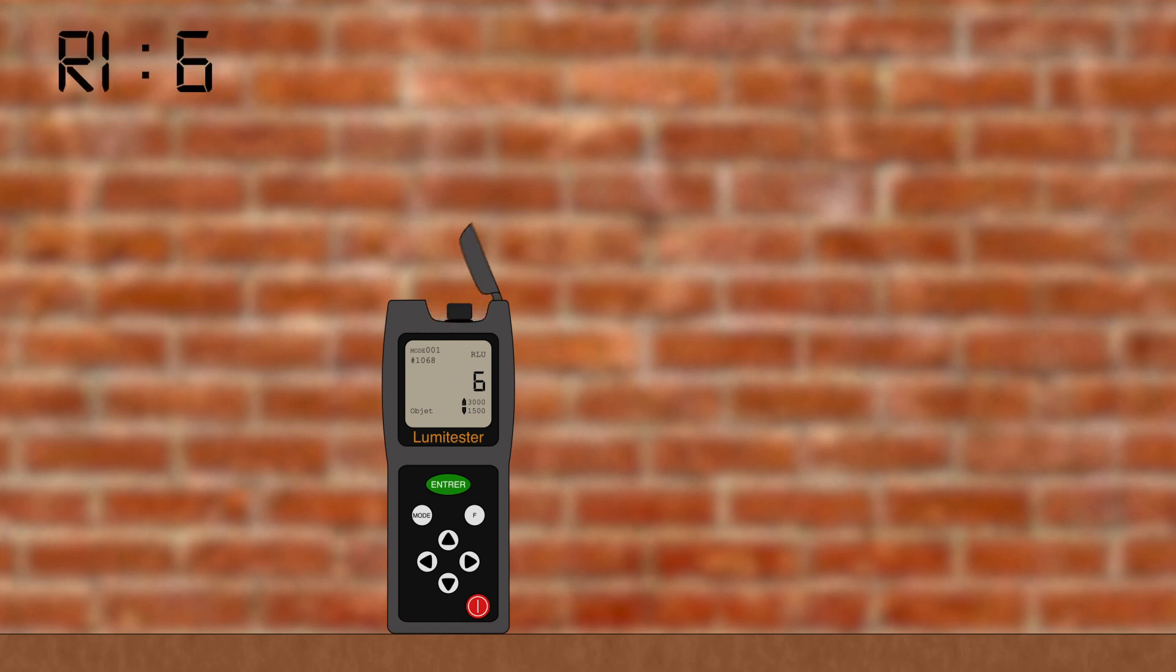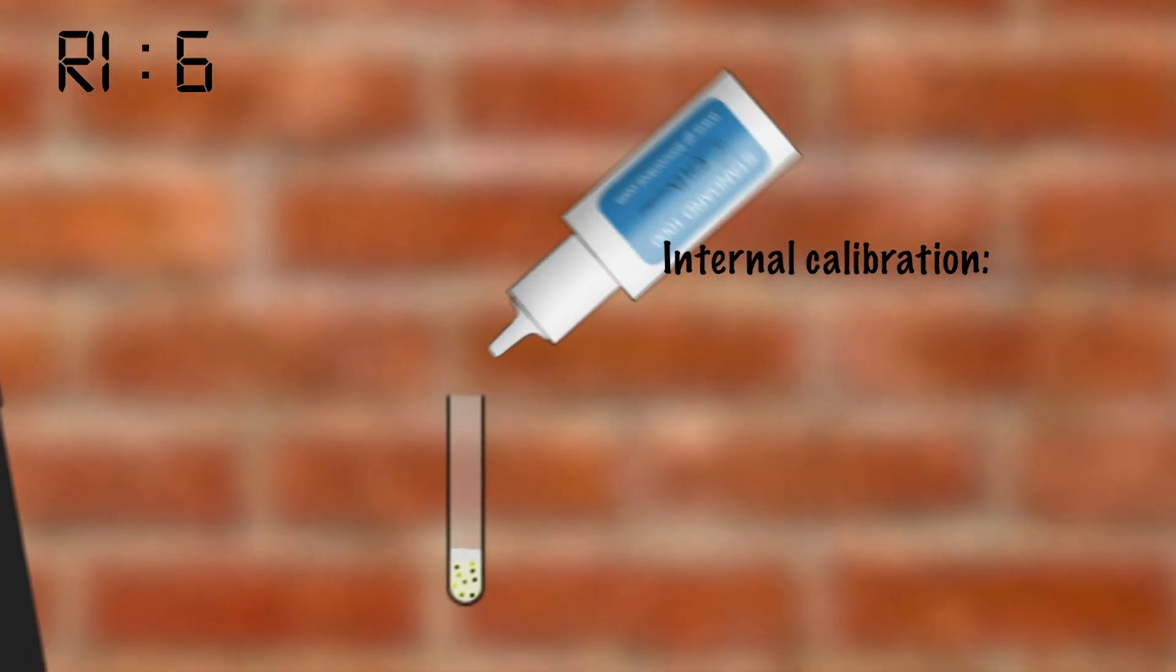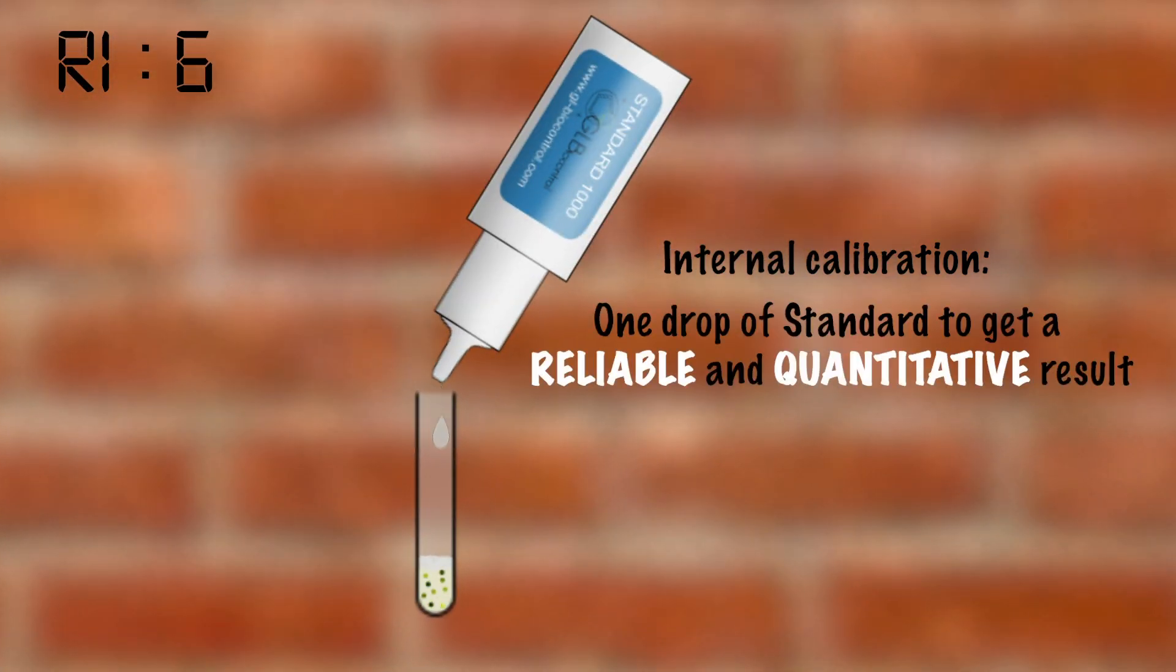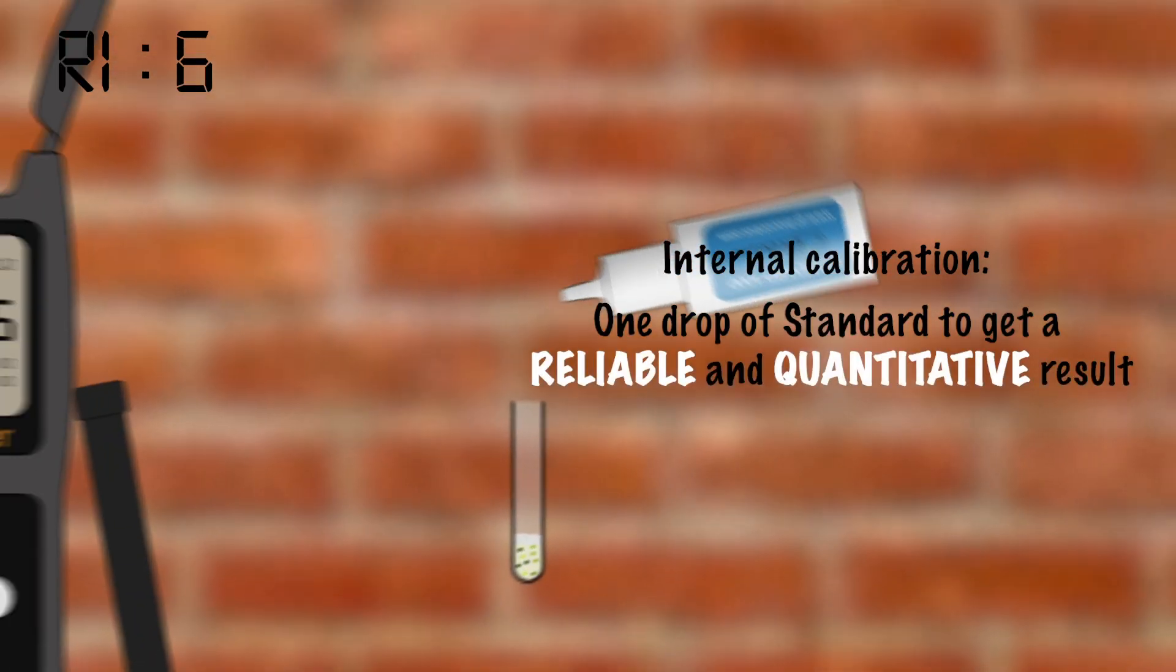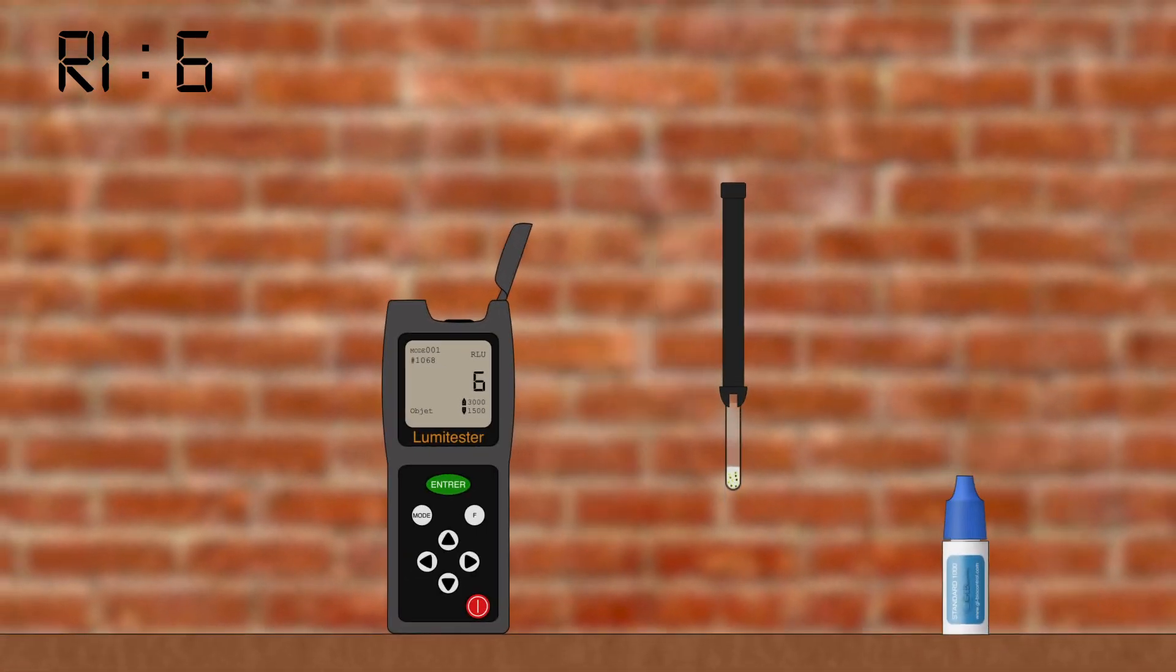Then, to get a quantitative result, we do an internal calibration for each analysis. Add one drop of standard corresponding to a precise quantity of ATP. Then perform a second measurement. Note the second result, R2.